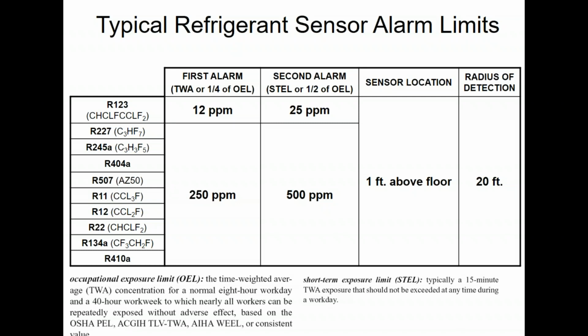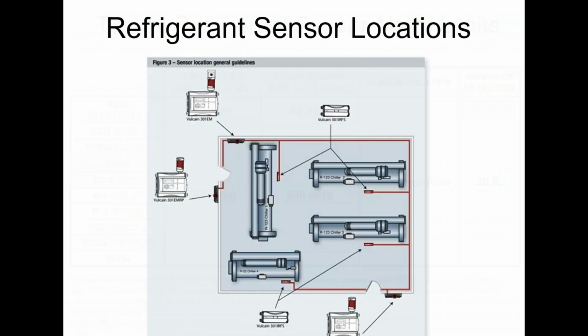All these refrigerant sensors need to be mounted down near the floor because generally speaking, refrigerant is heavier than air, so it'll accumulate and pool down by the floor. So typically mount them 1 foot above the floor. Each sensor, for most manufacturers, handles about a 20-foot radius of detection, which for the most part means 1 sensor per chiller. I guess if you had 2 chillers right next to each other, you could stick 1 sensor between them. That does happen in some cases, as long as they're the same refrigerant. But generally speaking, it's a 1-to-1 relationship.